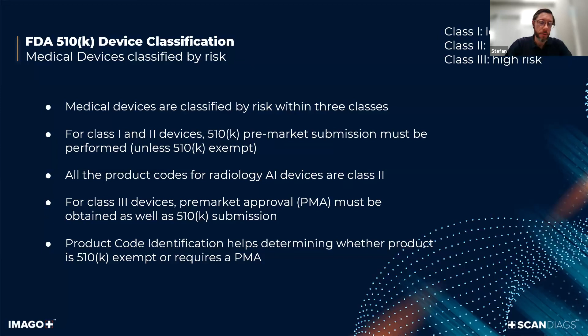So FDA, for all the radiology software solutions, AI-based software solutions, introduced different product codes that are different categories, and those devices have similar intended use, and therefore are in the same category. Now, in our case, our software corresponds to an automated radiological imaging processing software.